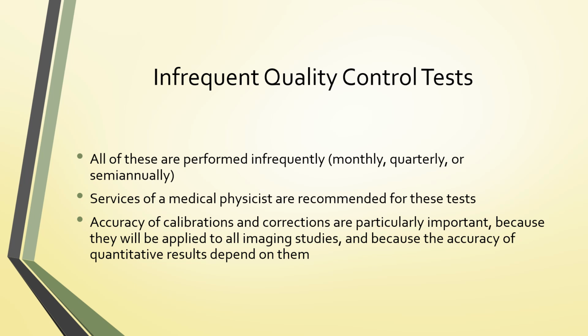Accuracy of calibrations and corrections are particularly important because they will be applied to all imaging studies and because the accuracy of the quantitative results depends on them. Especially if you're doing SUV calculations, myocardial blood flow, it's really important that the scanner have all of the calibrations and corrections where they need to be so that errors are not introduced into the images.